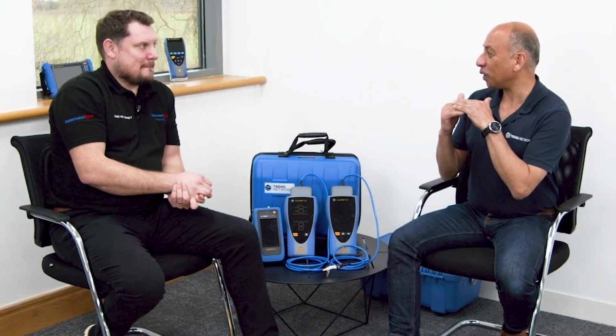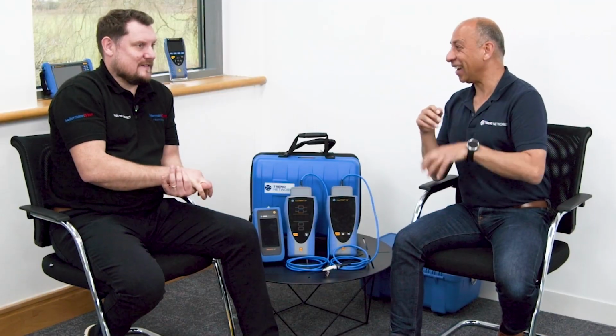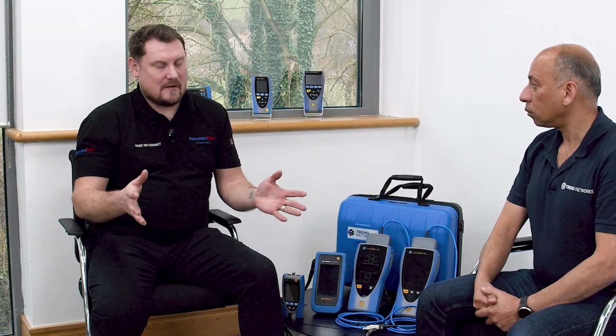Yep, electrical cables very often get added into pathways. I think one of the main problems from that perspective is not only looking into the expansion you might require in the future, which is obviously very difficult to determine, but if we focus solely on, say, the Ethernet twisted pair cabling, so Cat6, Cat6A, you actually have to separate those from power as well. Most of the time, the containment sees those cables sharing the same space. So as well as future expansion, you need to also allow for separate power and data separation.